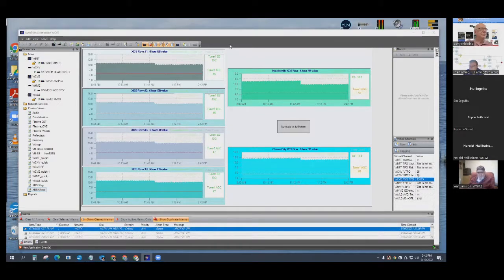I've got a comment about a linked pressure sensor on Amazon. Yeah, you just do a search for pressure sensor. They seem to constantly change. They're Chinese units, but we've had ours for about 2 years and they seem to work reliably, and literally they were 20 bucks. It's just getting the right fittings on the end—I believe it's a 3/8 OD fitting that's most common. $20, and then it's voltage in and pressure out, so look for something in the 0 to 15 psi and 0 to 15 volts DC kind of range.